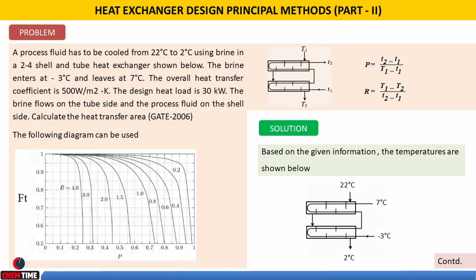Coming to the gate problem. A process fluid has to be cooled from 22°C to 2°C using brine in a 2-4 shell and tube heat exchanger. The brine enters at −3°C and leaves at 7°C. The overall heat transfer coefficient is 500 W/m²·K. The design heat load is 30 kW. The brine flows on the tube side and the process fluid on the shell side.